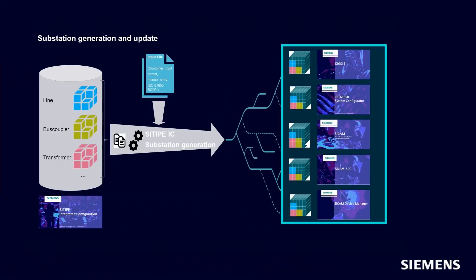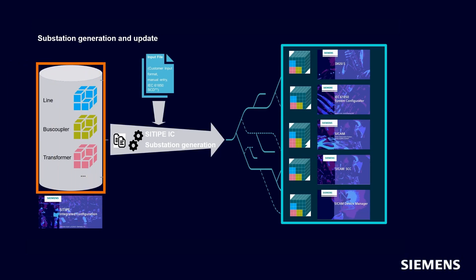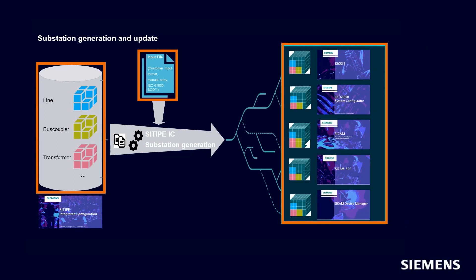SITIPE IC is able to generate a substation configuration based on bay templates like line, bus coupler, transformer, and others according to substation configuration file. You can get complete configuration files such as DIGSI 5 IEC 61850 S-Configurator, SICAM PAS, SICAM SCC, and SICAM DeviceManager out of it.